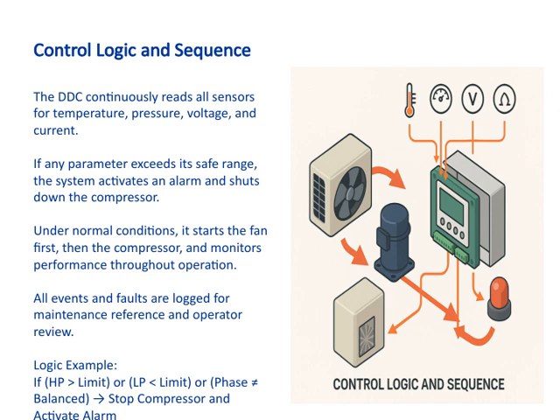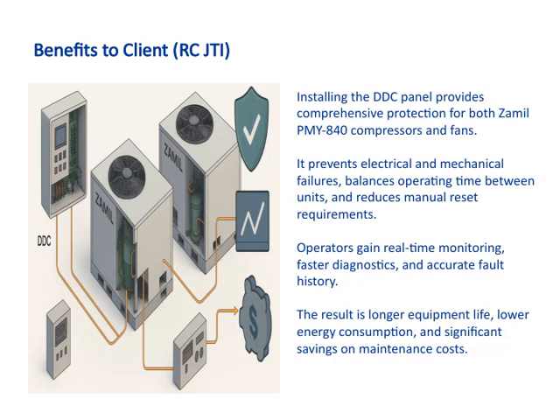Installing the DDC panel offers comprehensive protection for the Zamil PMY-840 compressors and fans, which is a key benefit. It helps prevent both electrical and mechanical failures, ensuring the equipment runs smoothly and reduces downtime. By balancing the operating time between units, it also promotes more evenly distributed wear and tear, extending the lifespan of the equipment. Another important advantage is that it reduces the need for manual resets, saving time and effort for operators.